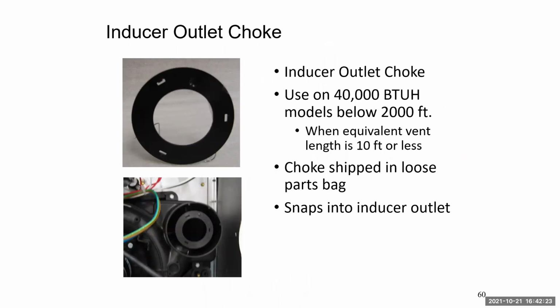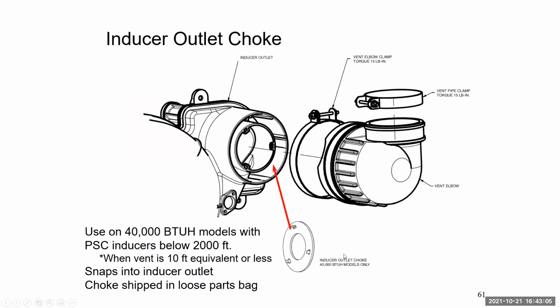Outlet chokes. 40,000 BTUs, and you're under 2,000 feet of elevation, and your pipe's going to be short. You're going to put a choke in there. That choke comes in your loose parts bag, and it snaps right in. If you look at that bottom picture, you have your main outlet, and then internal is that second circle. You'll see those notches there. That choke has clips on it, and it'll clip right into those notches, and you're off and running. Again, when to use it is 10 foot or less at 2,000 elevation or less on a 40,000 BTU unit. Read your manuals when you're putting stuff in, and you'll know if you need that or not. If you have questions, call us.